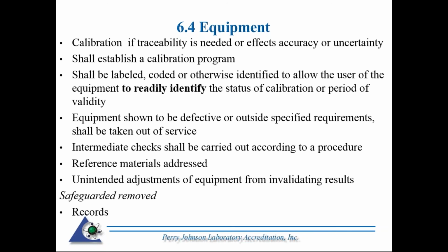So as an assessor, if I'm looking for the calibration status of a particular piece of equipment that I'm witnessing in action, it is something that I want to see rather quickly. And if you're still labeling them, i.e. by a physical label, then that of course will be readily available. However, it's not a requirement anymore. Specific requirements still in place about removing equipment and taking it out of service. Same requirements about intermediate checks. Reference materials are addressed in 6.4. Unintended adjustment, the only change there: it used to say safeguarded, now it specifies unintended adjustments. And equipment records. Those records, I believe, are verbatim from 2005, but you are still required to maintain records of your equipment.